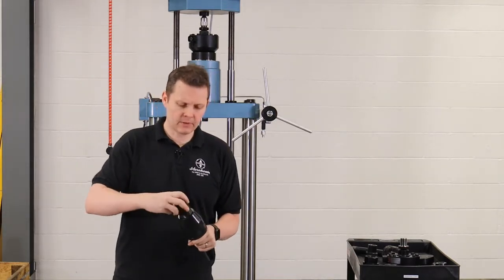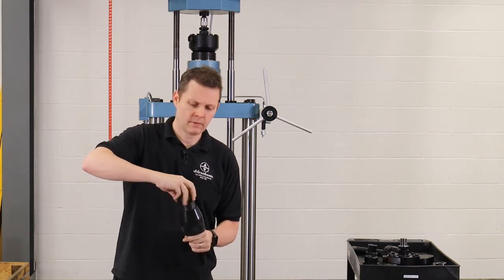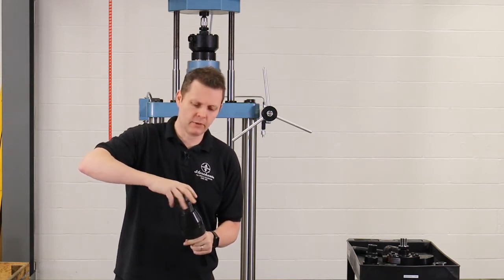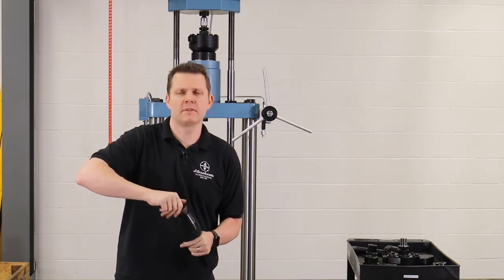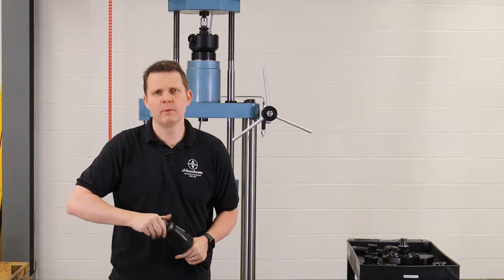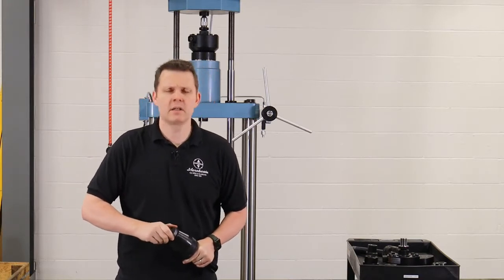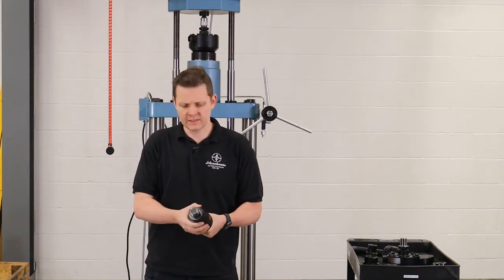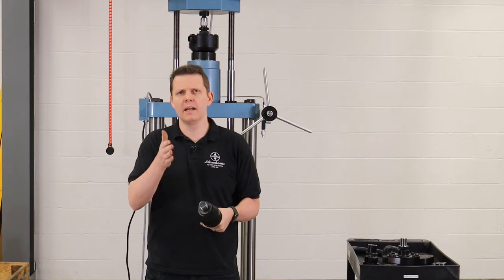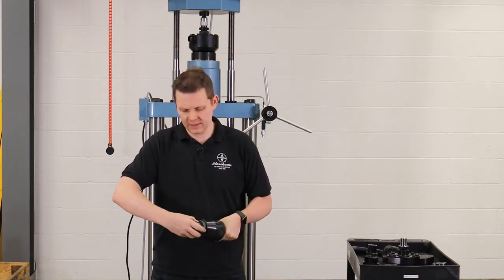So these adapters are simple. They screw into the quick change adapters, screw into the tension member, and you can use all types of sizes. People use threaded rod, eye bolts, rod ends, all types of different things, and this simplifies things, aligns the force. You just switch this piece in and out and I'm going to take this one out and mount this load cell here.